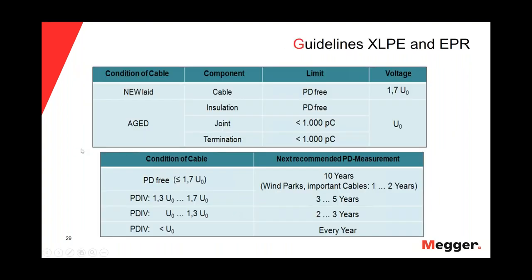We have guidelines for the partial discharge test. For aged cables in a maintenance partial discharge test, the insulation must be PD-free. In a maintenance test, we should have no partial discharge in the insulation of the cable. But for splices and terminations, we can allow up to less than 1,000 picocoulombs for aged cable splices and terminations. We have different guidelines that we can use to make a decision after performing a partial discharge test.